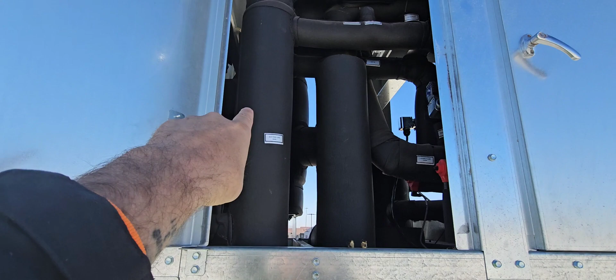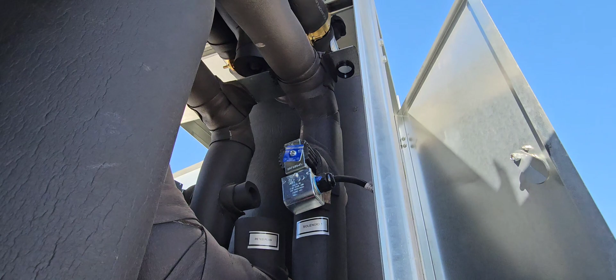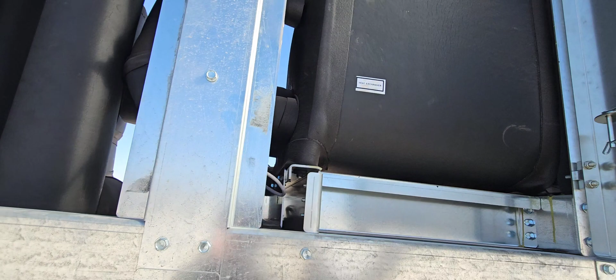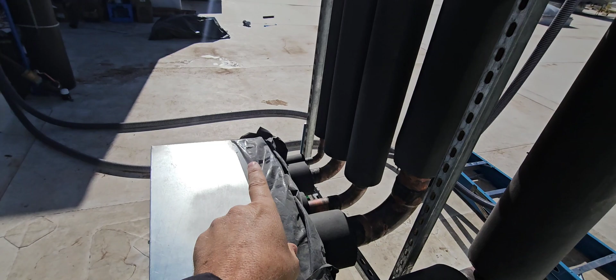What happens is those refrigerant lines come in. So there's my liquid, goes through an inline heat exchanger, liquid comes in. We go through our solenoid, through our EEV, into our heat exchanger. And then suction comes out at the top, comes back into our inline heat exchanger, back to the rack, which for this is going in, under, and then it's gonna pop up into the rack.